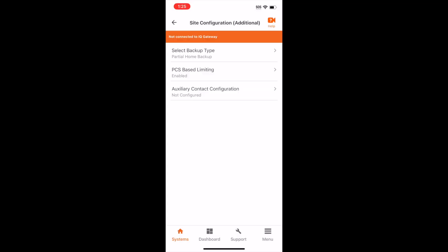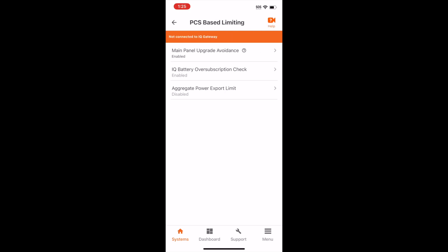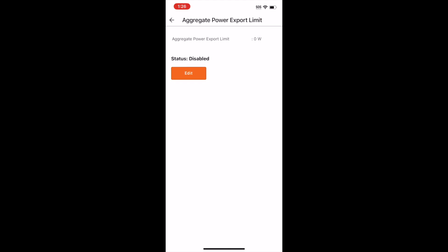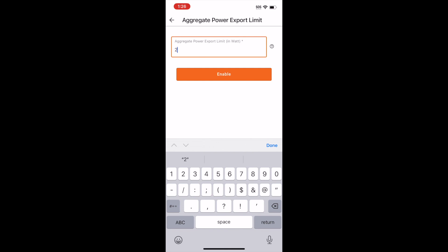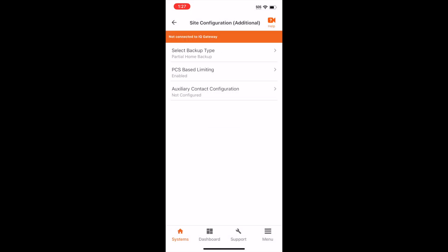If your site has a requirement for an Aggregate Power Export Limit, navigate to the PCS Based Limiting Options. Tap Aggregate Power Export Limit. Tap Edit. Enter the value in watts as required for the site. Commission the system, and you are done.